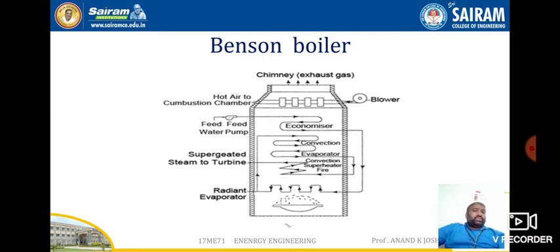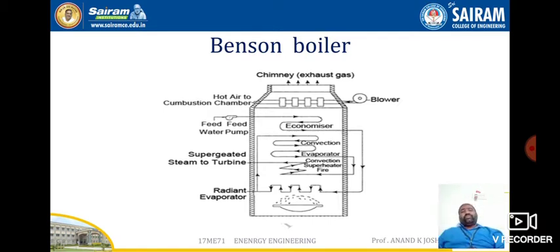The Benson boiler is a type of forced circulation boiler. Combustion takes place at the bottom of the Benson boiler, and at the top a chimney is provided to discharge the exhaust gases. A blower is also provided. There is a combustion chamber with hot air, and feed water is supplied for generating steam. An economizer, convection section, and evaporator are provided. The superheated steam obtained is used to expand and produce mechanical work, which is then converted to electrical work through turbines.